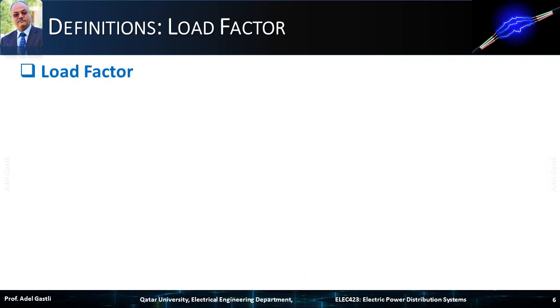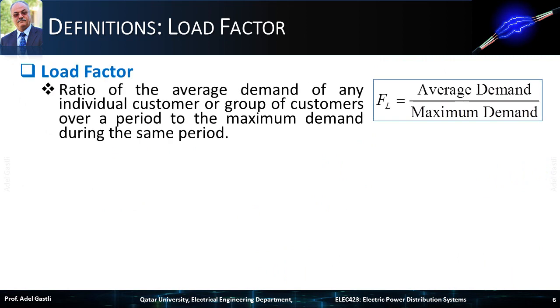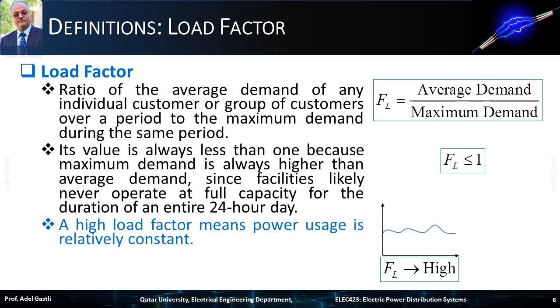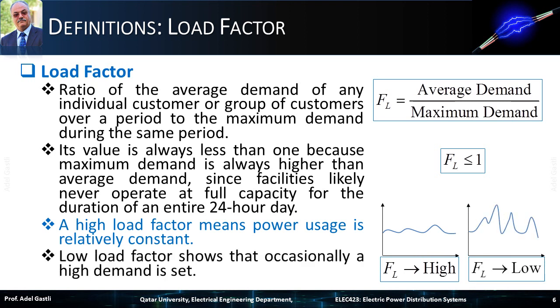Next, we will define the load factor. The load factor is the ratio of the average demand of any individual customer or group of customers over a period of time to the maximum demand during the same period. Its value is always less than 1 because maximum demand is always higher than average demand, since facilities likely never operate at full capacity for an entire 24-hour day. A high load factor means power usage is relatively constant, and a low load factor shows that occasionally a high demand is set.